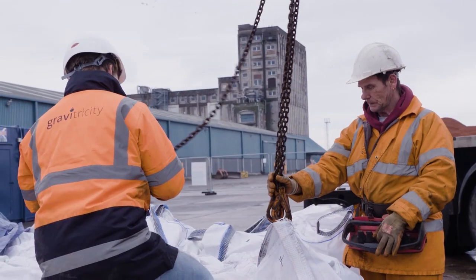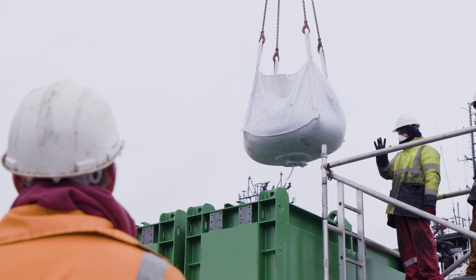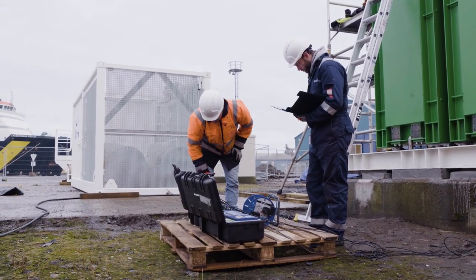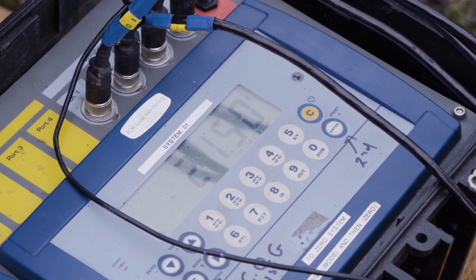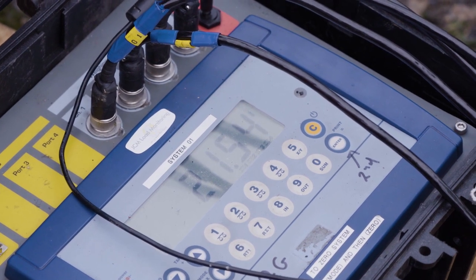Can you share some tech specs with us? Typically, we're talking individual weight units of around 500 to 600 tons. And in a typical European shaft, that will give us about a megawatt hour. So that typically is what the unit is. Our system is modular, and each individual system will typically have 4 winches, and each winch will typically have 4 motor generators. So you can stack that system up any way we like.